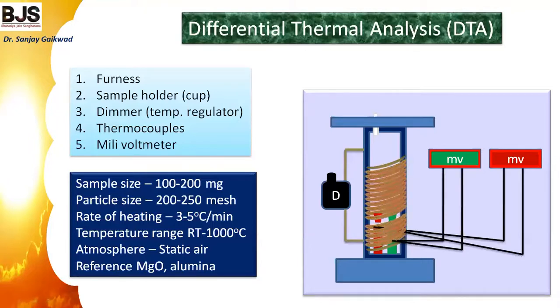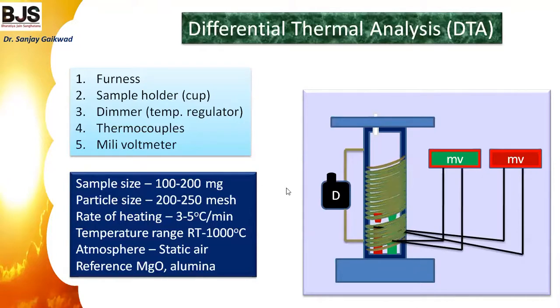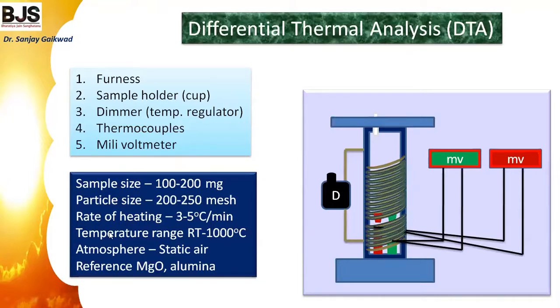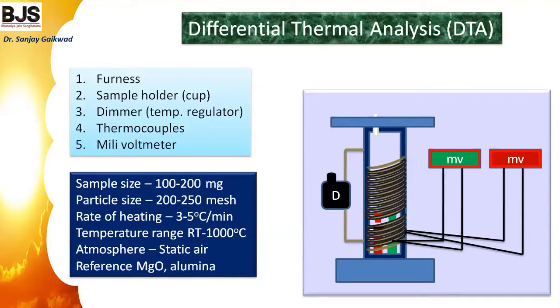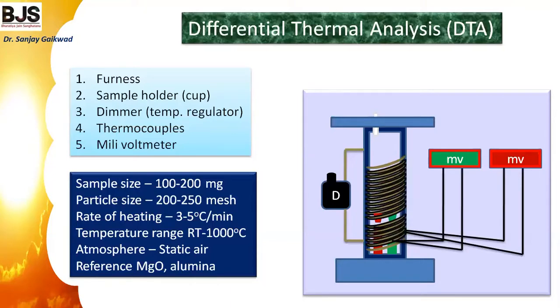The DTA instrument uses a furnace, sample holder, dimmer, thermocouples, and voltmeter. The sample size is similar to that used in thermogravimetric analysis. The same factors apply: sample size, particle size, rate of heating, temperature range, atmosphere, and reference compounds. The temperature difference between the two compounds is measured simultaneously, revealing whether reactions are endothermic or exothermic.